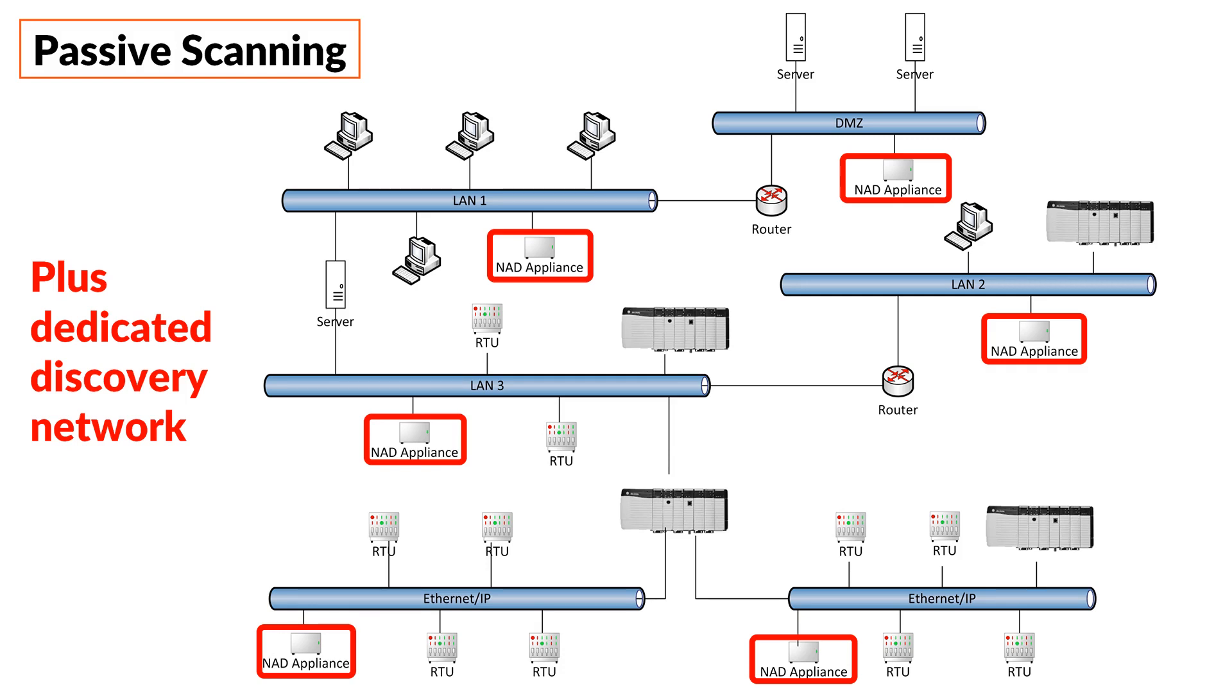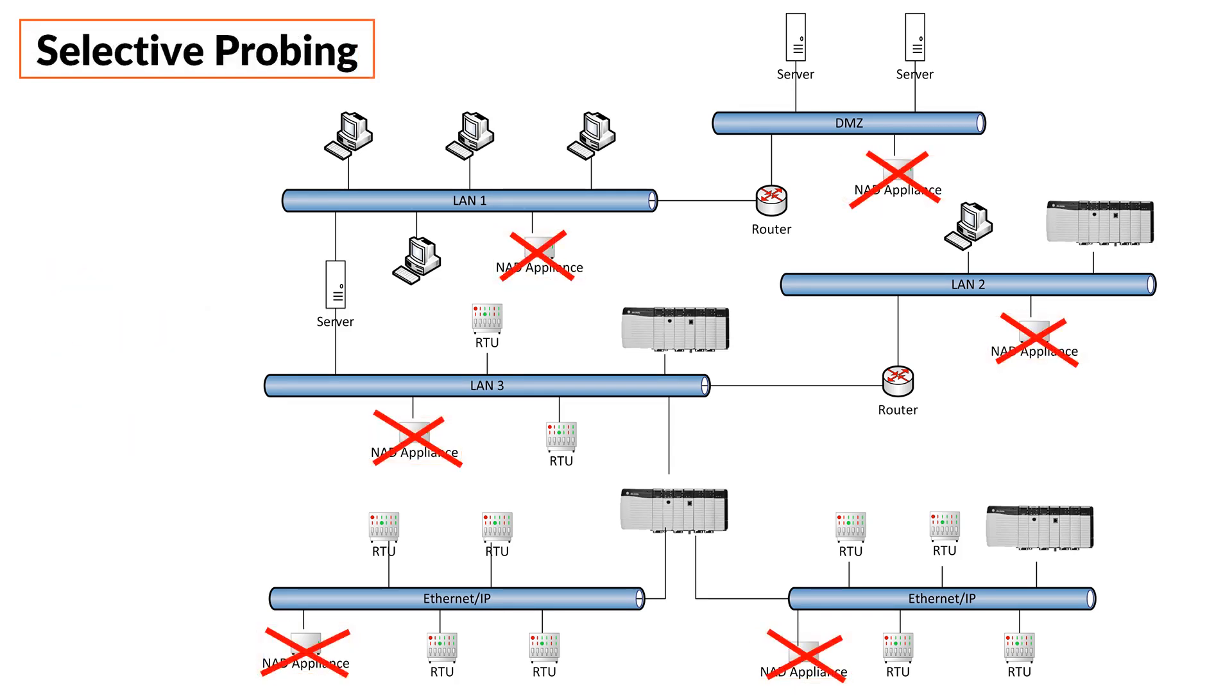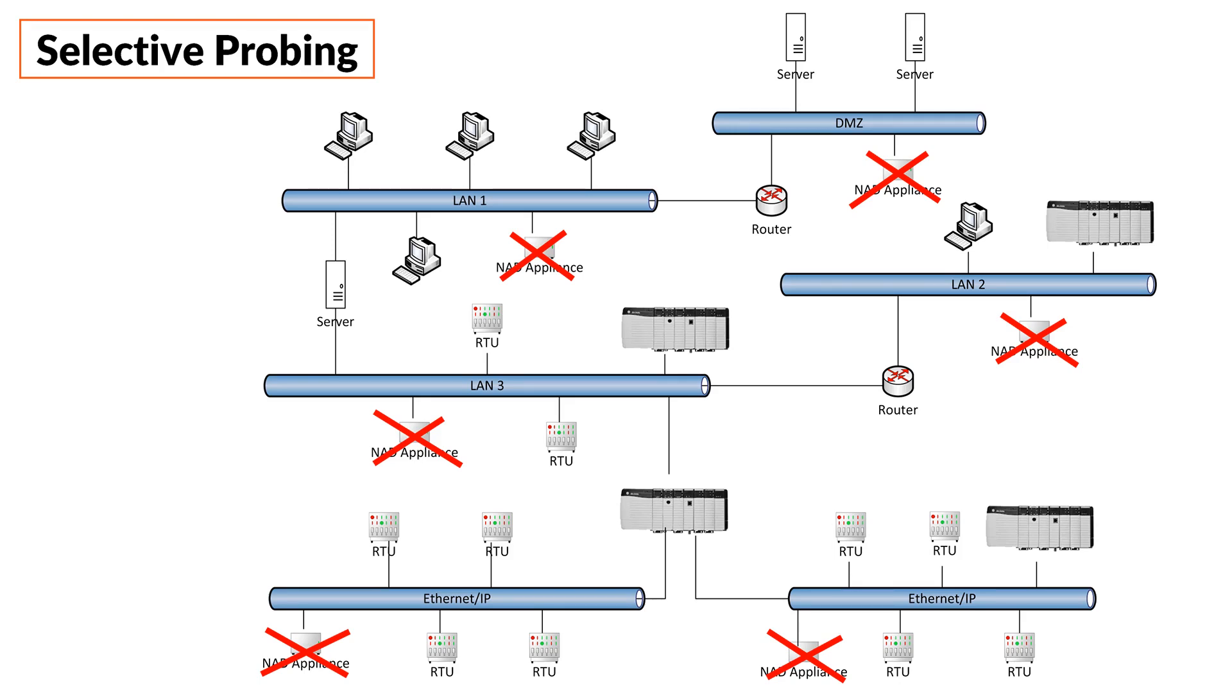Now, let's look at the alternative scenario, where we use selective probing instead. Selective probing is software-based, which means you don't need appliances in the first place, because the selective probing service can be run on a given hardware, such as the Windows server or such as an engineering station. Why is that possible? Simply because active probing is a small footprint. It can run, it can coexist with existing applications like an engineering application. So you don't need dedicated hardware appliances. And also this is possible because the probing process might just take hours. It doesn't matter. Whereas opposed to passive scanning, you need to be able to process real-time network traffic from all stations.